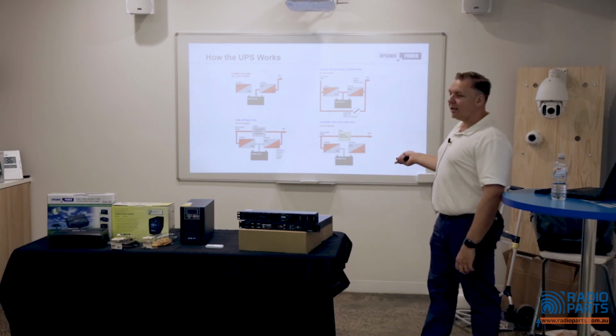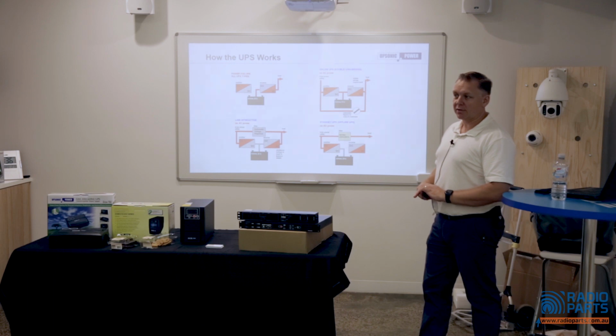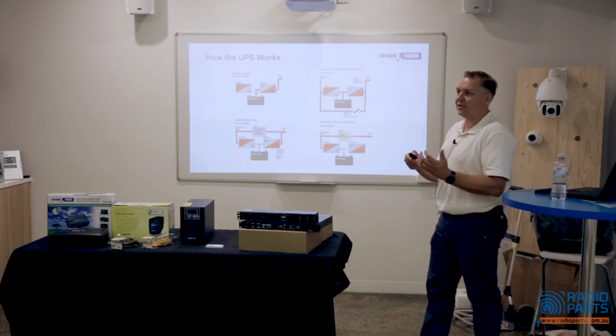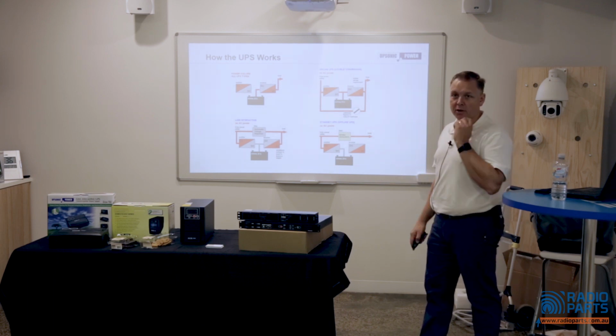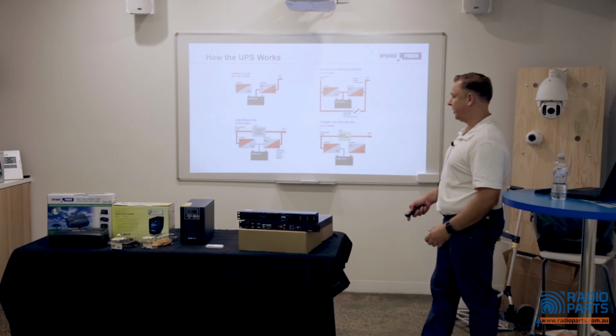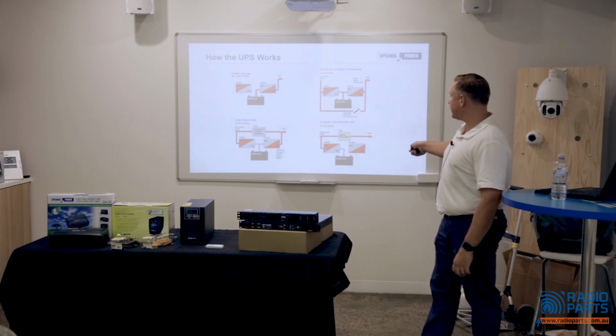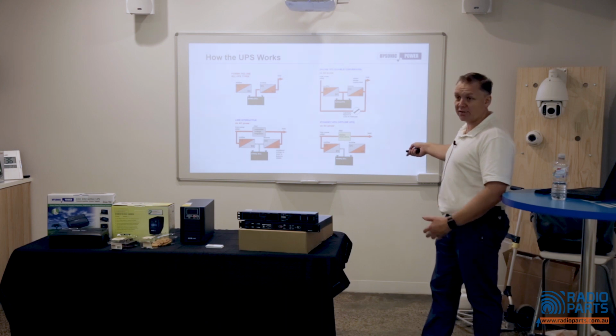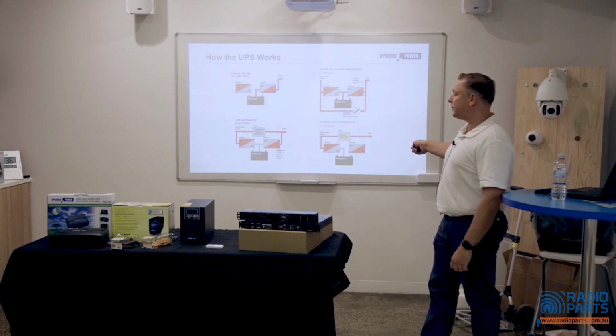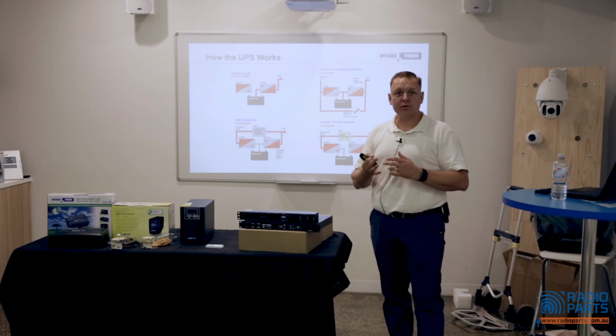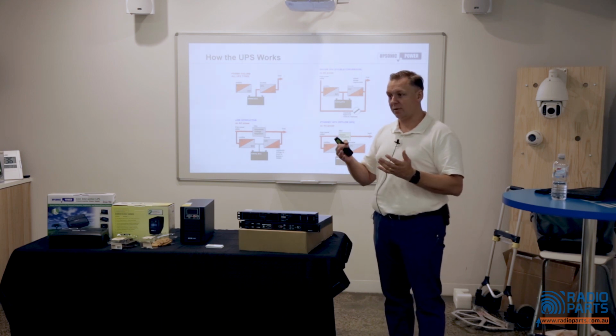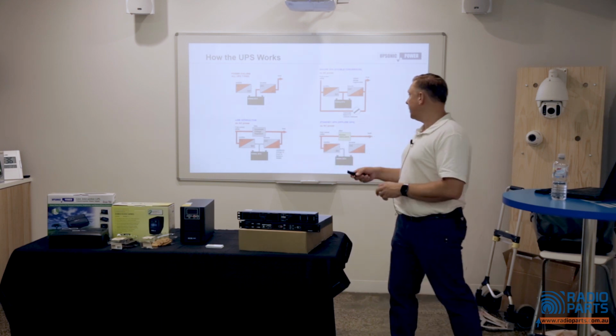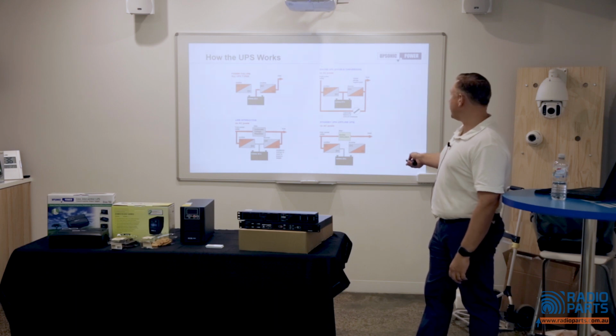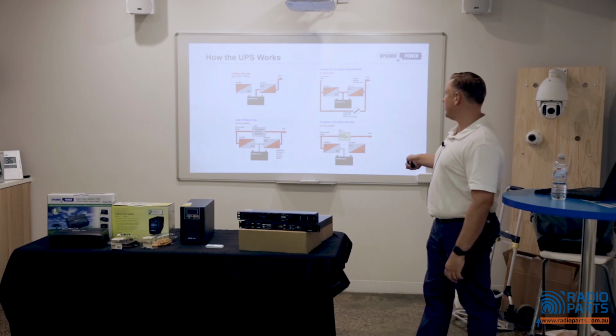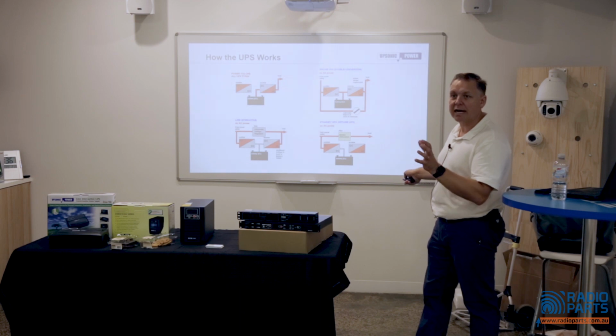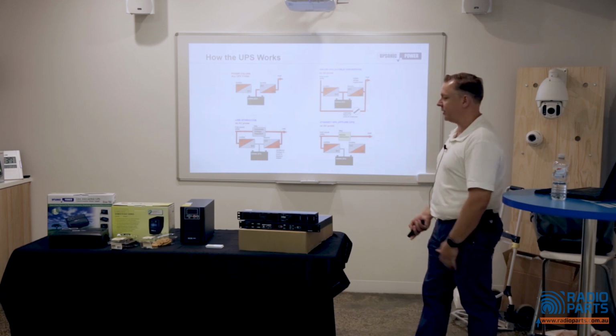this rectifier, all it does is charge the batteries. It doesn't do anything with actually supplying the load, so it's a fairly small component in comparison. The inverter takes the power from the batteries, converts it back to AC and supplies the load. There's also some electronics in there that provide some filtering and try and smooth out the output as best as possible. So our standby UPS just has a little filter in it. It can't do too much more than that. It's basic in concept.